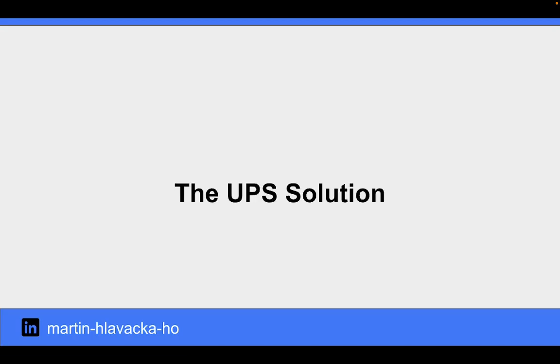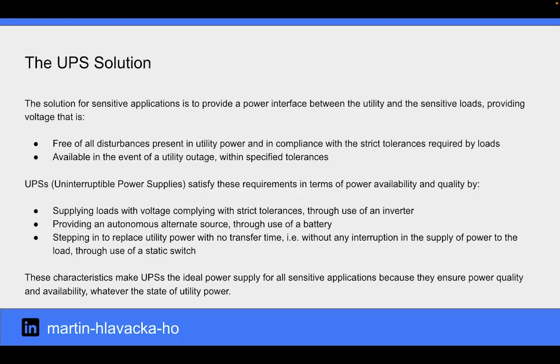The UPS solution. The solution for sensitive applications is to provide a power interface between the utility and the sensitive loads, providing a voltage that is free of all disturbances present in utility power and in compliance with the strict tolerances required by loads, and available in the event of a utility outage within specified tolerances.